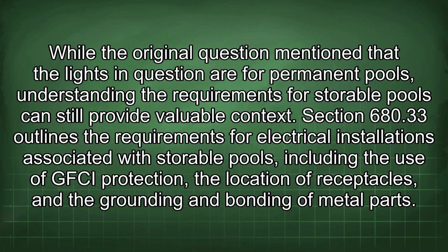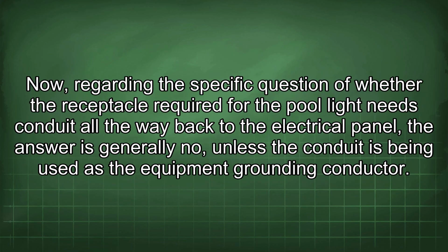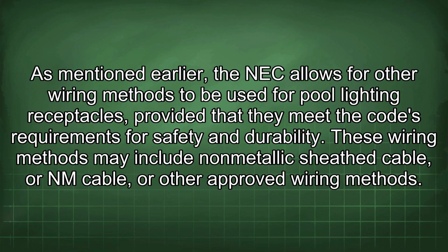Section 680.33 outlines the requirements for electrical installations associated with storable pools, including the use of GFCI protection, the location of receptacles, and the grounding and bonding of metal parts. Now, regarding the specific question of whether the receptacle required for the pool light needs conduit all the way back to the electrical panel, the answer is generally no, unless the conduit is being used as the equipment grounding conductor. As mentioned earlier, the NEC allows for other wiring methods to be used for pool lighting receptacles, provided that they meet the code's requirements for safety and durability.